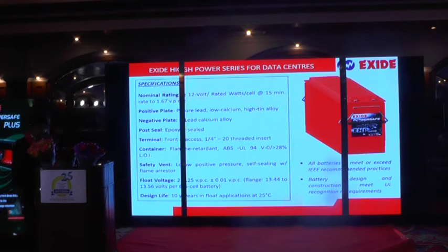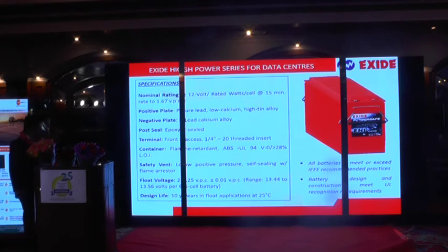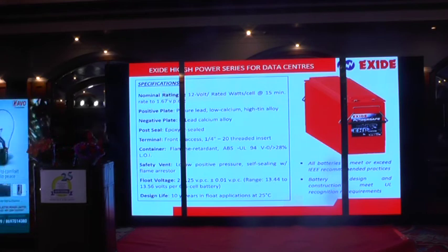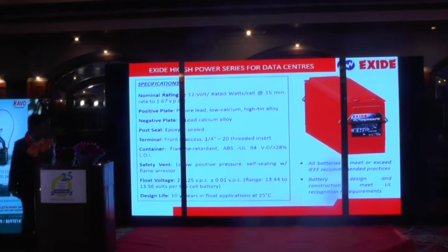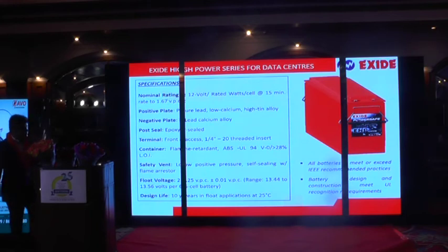The container is flame retardant ABS, which meets the UL94 V0 specifications. So this battery has been developed taking into consideration the full safety and reliability aspects. The safety vent is a low positive pressure self-sealing valve. We recommend from Exide to keep a float voltage of 2.25 volts per cell, and the design life is 10 years at an ambient of 25 degrees centigrade. This product meets all stipulated guidelines of IEEE 485, and the battery design and construction meets all the UL requirements.